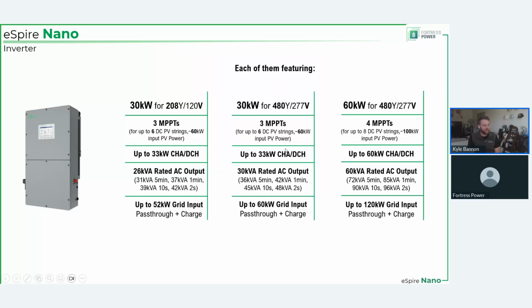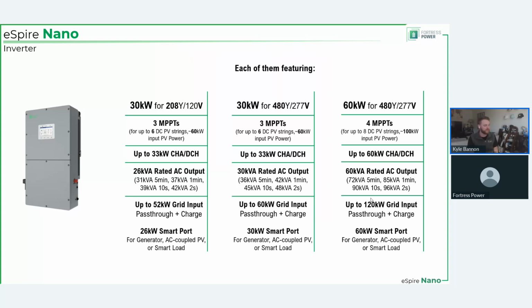Pass-through. Each inverter does have a fair amount of pass-through. For the 30 kW 208, you're talking 52 kW, but for the 60K 480 volt, you're talking up to 120 kW of grid input that's passed through and charged. So a lot of flexibility here. You don't have to rely just on the inverter itself to cover all this stuff. You get a fair amount of pass-through there.